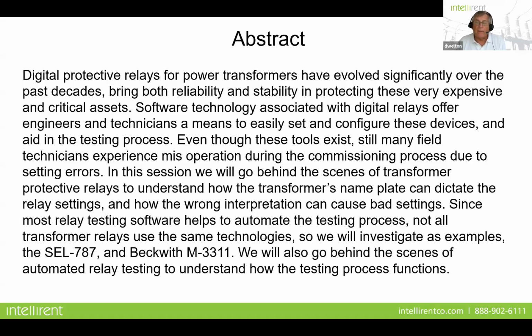But if you look at statistics that show why relays fail, and we're talking about modern digital relays, the biggest reason is that they're not set properly. And by setting, I'm not talking about just pickup, dropout and time dials of a certain protective element, but also the logic and the configuration of these devices. Because the more protective elements you put into a relay package, the more chances are that something didn't actually get set properly. And sometimes in the commissioning process, that's hard to find.